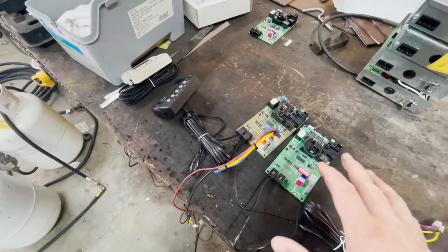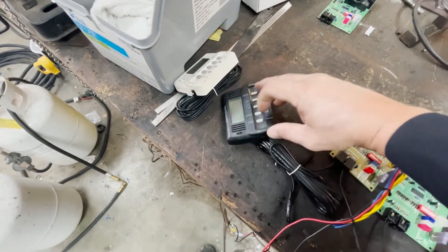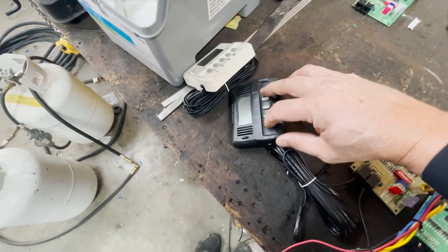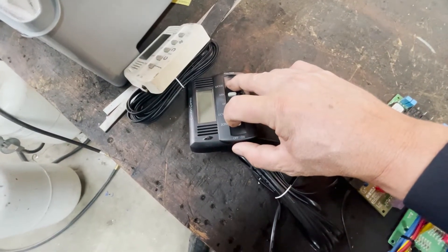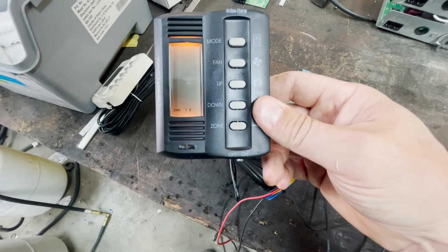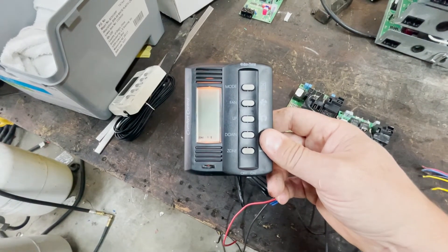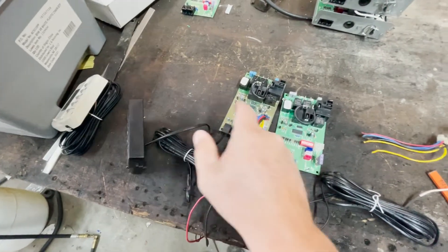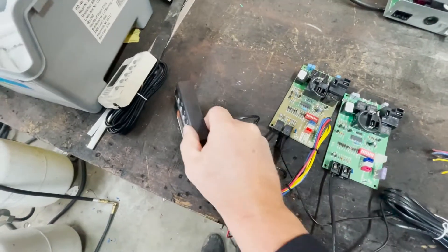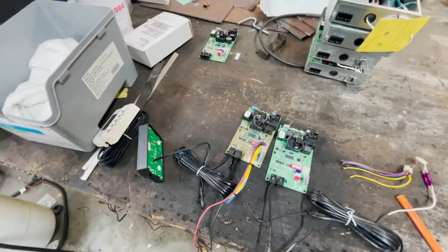So I've got them wired up now, got the phone cables connected to that. A 10-button thermostat is going to be different than a five-button or a four-button thermostat. Before we do anything, we've got to initialize — I've got to hold these two buttons right here, the mode and the zone button, simultaneously while turning on the switch. You'll see we got an FF. If everything goes good, which it did, you'll have zone one and zone two. Now if we had an EE, then we'd have a communications error between the thermostat and the control board. Keep in mind that if we had a problem with zone one or zone two, we could possibly only see one of them. So kind of some troubleshooting stuff we've got to do.